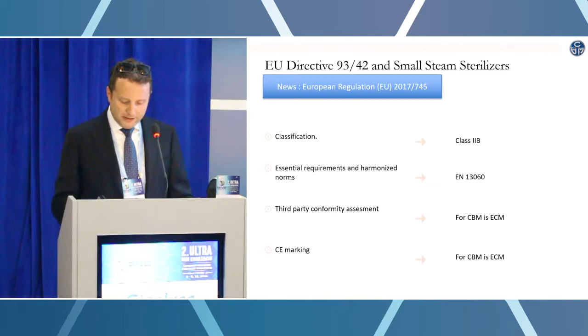So, what is important to know about this norm? This norm gives you information about the type of load, the definition of load: solid, porous. Solid means it cannot retain water or air inside. It has no recess, no small lumen inside. Practically, as you can see from the picture, from the odontoiatric point of view, we are speaking about scalers, mirrors, so very simple devices. Porous, of course, is whatever can retain water, so gauze, sponges, whatever, where air can remain trapped inside.